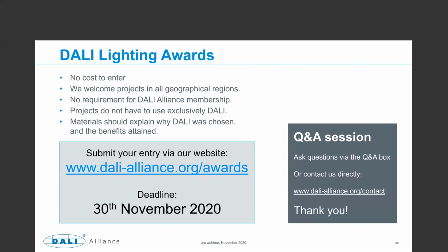With DALI, you've got a scene command which, within about 15 milliseconds, can change the light levels for all the lights in your system simultaneously. So no delay, no popcorn effect—it's instant. That one command affects all control gear, all luminaires together. Whereas with DMX, you'd have to go through a complete cycle, which is about 40 milliseconds.